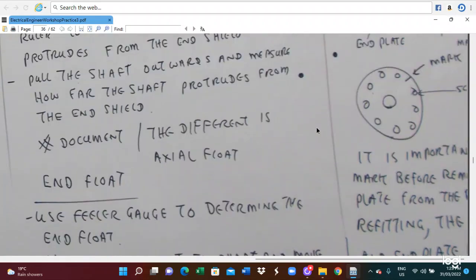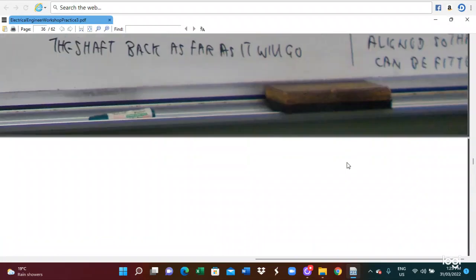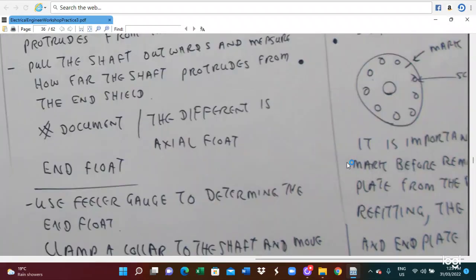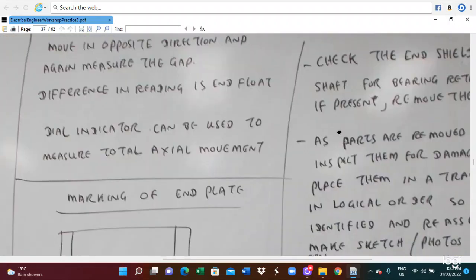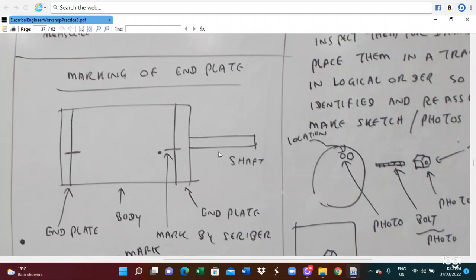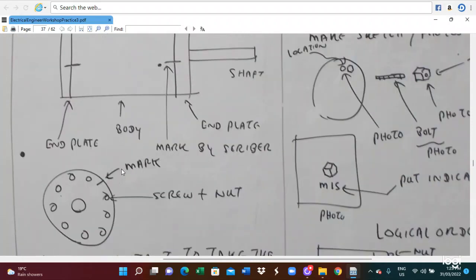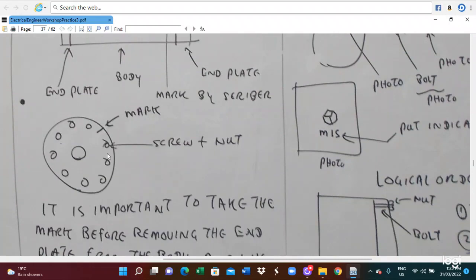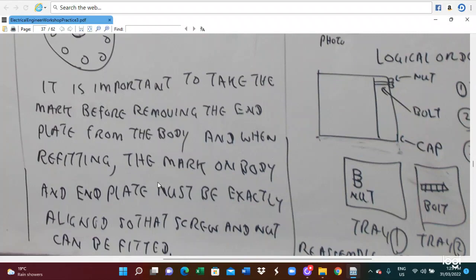So here we utilize a marking of the end shield. Before you are dismantling, you have to measure the marking. For the marking of the end shield, mark on the end shield and on the body, with an appropriate mark, also for the screw and nut. So this is important: take the mark before removing the end shield from the body.